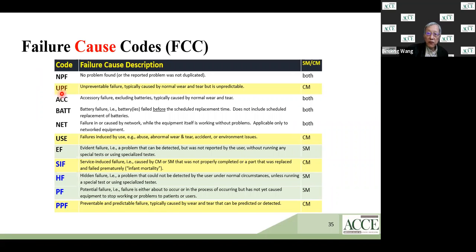Okay, unpreventable failure is typically normal wear and tear, and it's unpredictable. And this is the most common electronic failure for solid state electronics. Accessories, of course, batteries, okay, and network. Nowadays, a lot of equipment is networked, and very often a piece of equipment appears to be not functioning well, but actually the problem is the connection with the network and the server, etc.